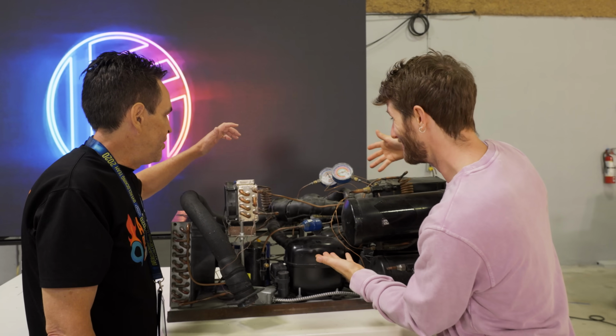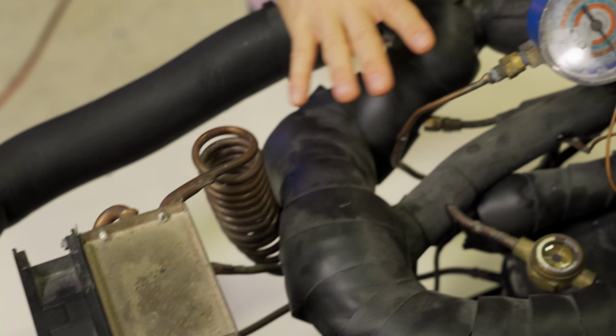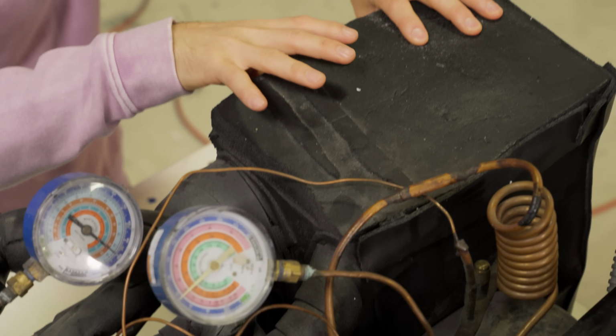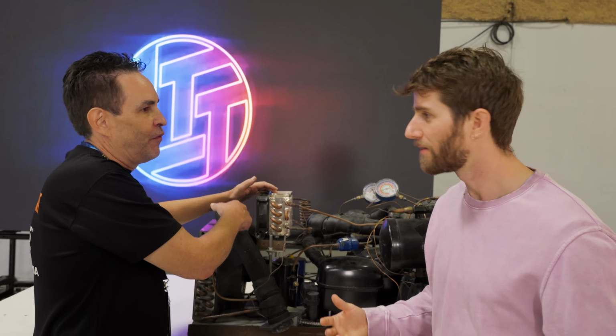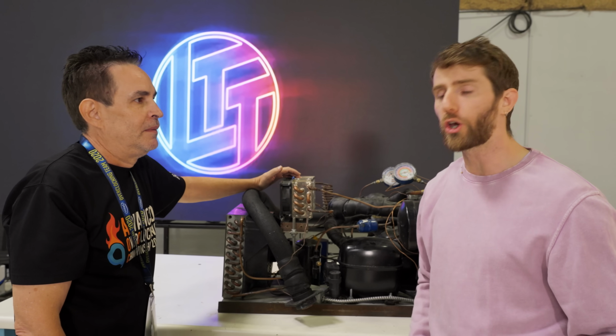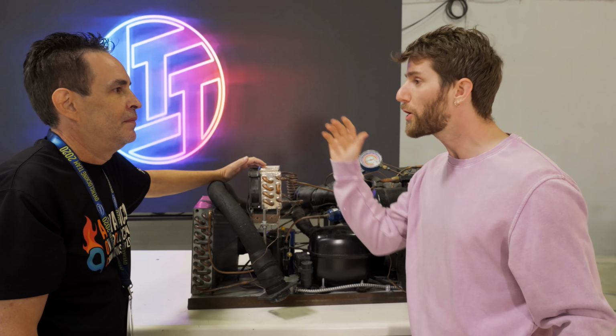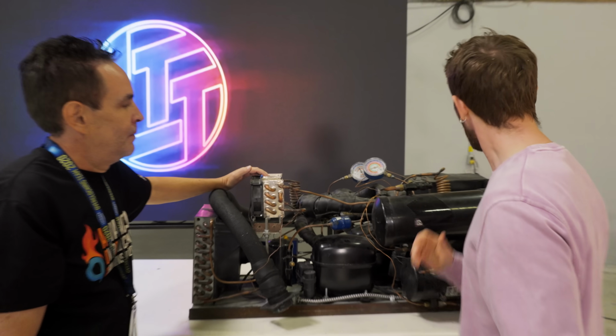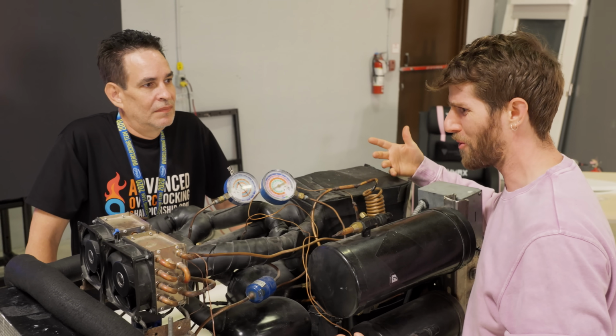The hot side goes into what's called a desuperheater first, before it even goes into the heat exchanger. So I'm actually stripping off the heat before it goes into the heat exchanger, to make it easier for our first stage to cool it and condense, correct. I'm bringing it down to ambient, so we pre-cool it. Brilliant, so where does it go from there?